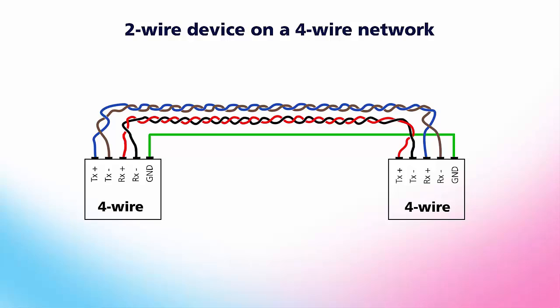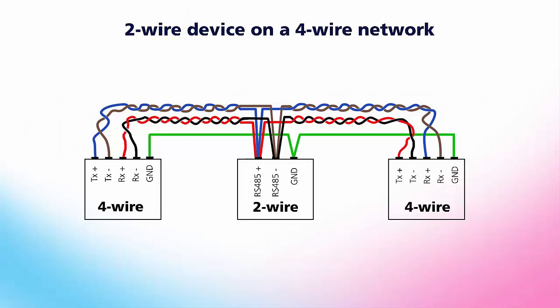If you have an RS-485 four-wire network but want to use a two-wire device, you can simply tie the two positive signals together and the two negative signals together at each device, and you'll have a two-wire device communicating over four wires.